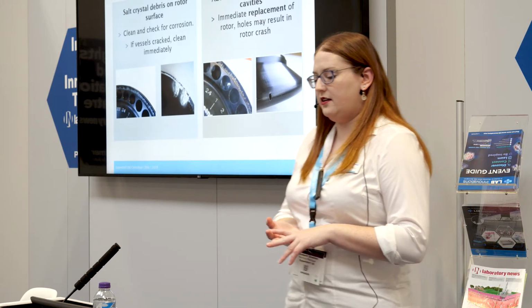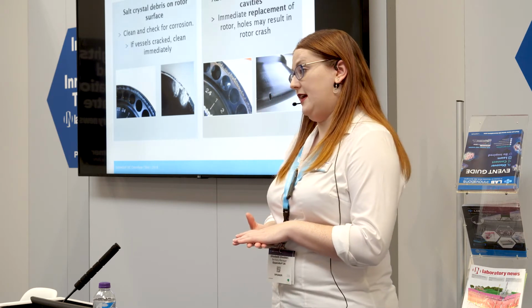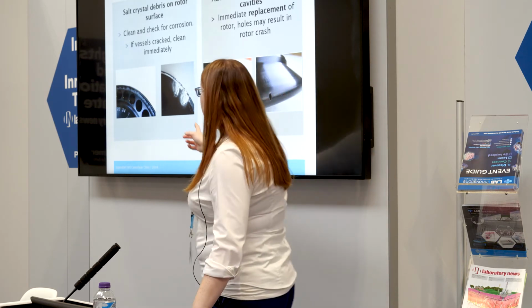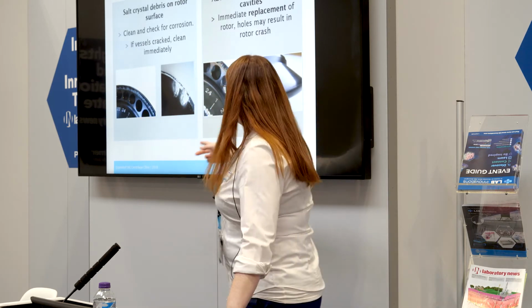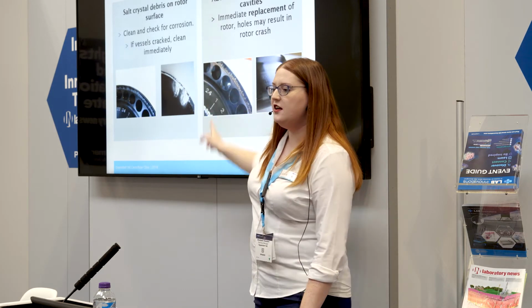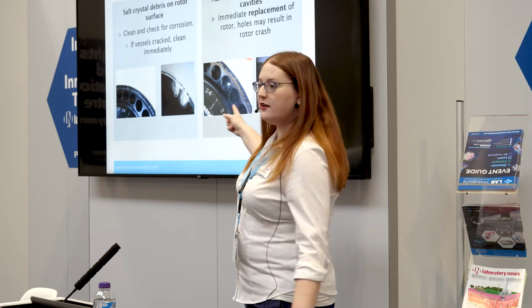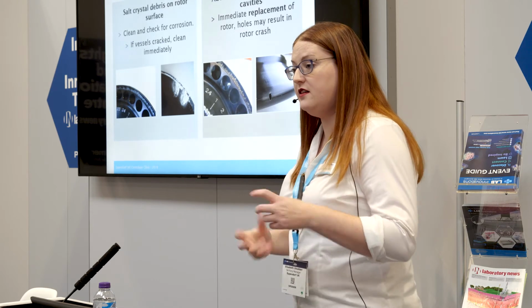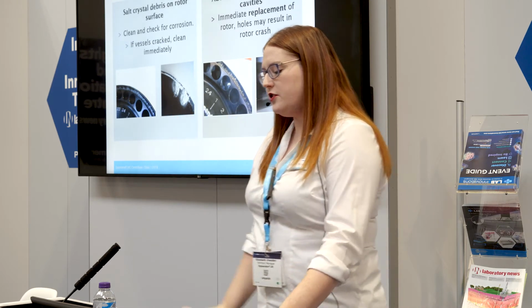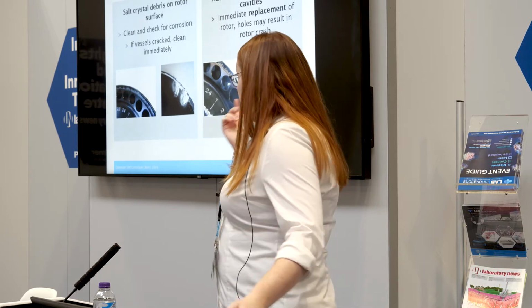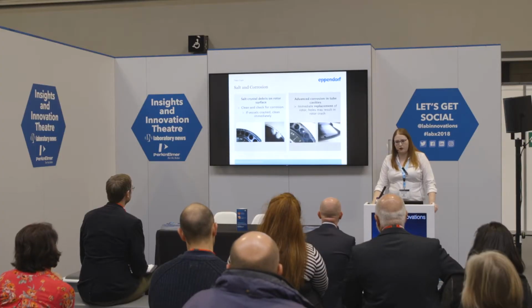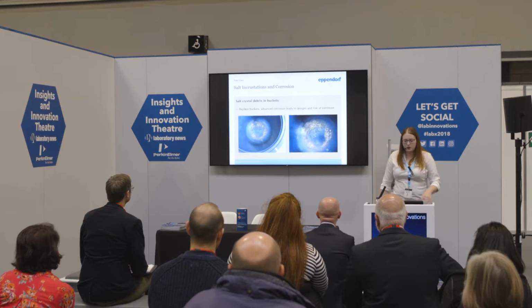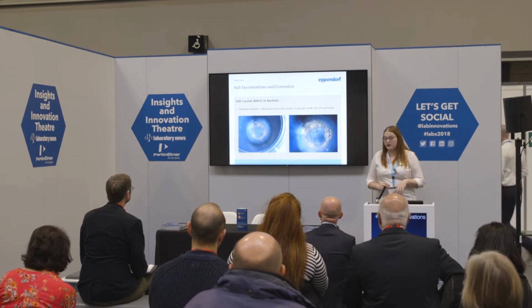If you are getting salt debris building up on your rotor, clean it. Check it regularly, look for things like this, and clean it up. If you start to see daylight through your rotor, don't ever use it again. This is a photograph of a rotor where the customer hadn't taken it out of their centrifuge since they bought it, and had no idea there was a hole in it because they never took it out. When we inspected it, we could see daylight through it, so we took it off them and never gave it back. Also look at things like debris in the buckets, because people don't check for that.